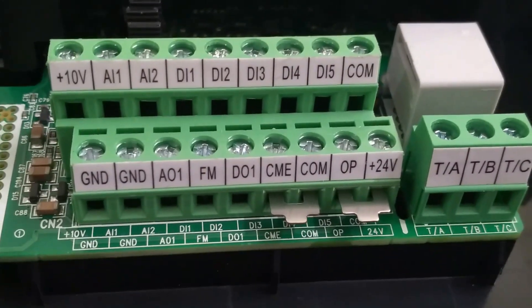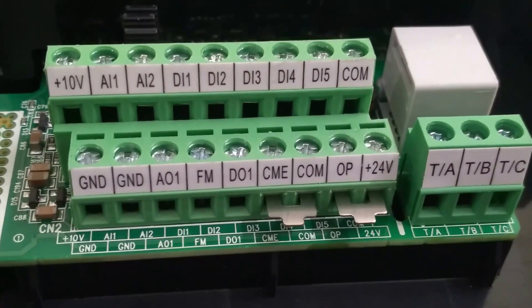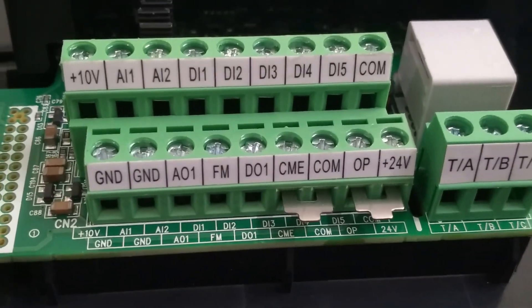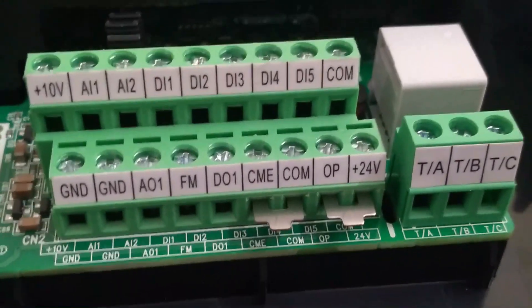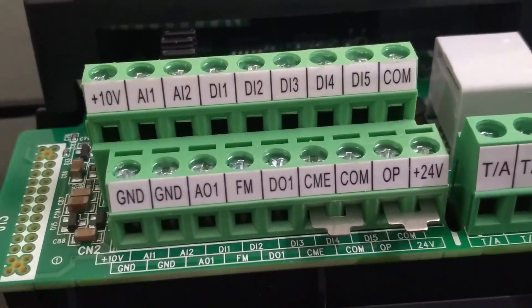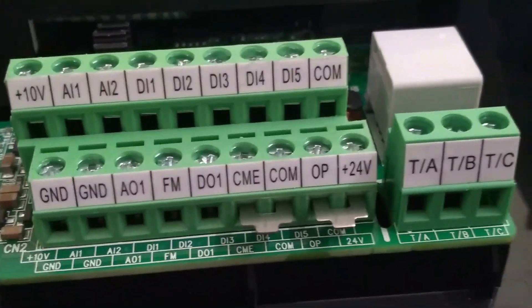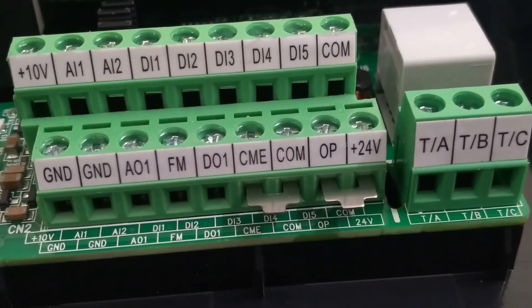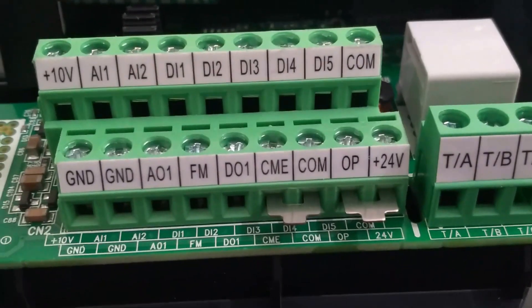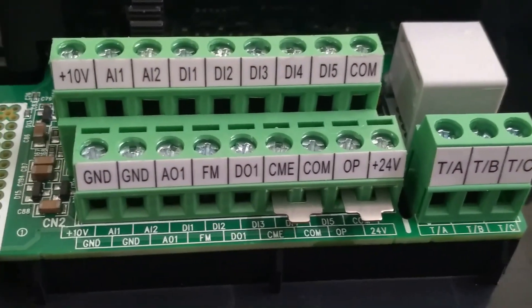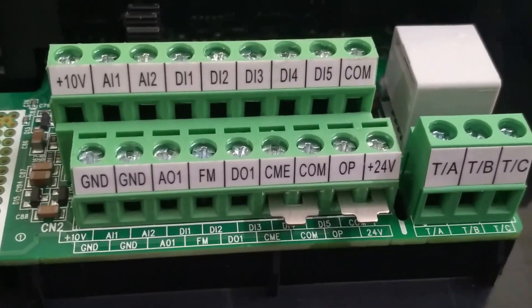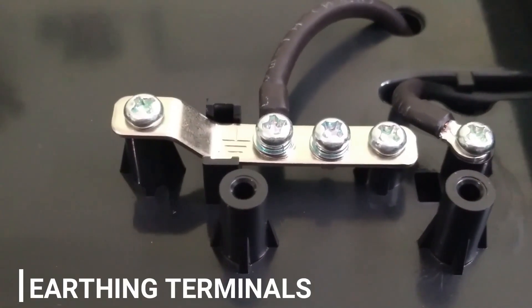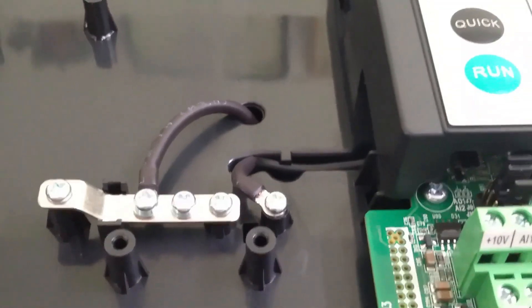DI1 to DI5 are digital input terminals and DO1 terminal is digital output terminal. At the right side of control terminal block, we have relay output terminal marked as TA, TB, and TC. Here TA terminal is a common point of relay, TB is NC point of relay, and TC is NO point of relay. By default, relay is programmed for VFD fault condition. These are earthing points of control terminals.